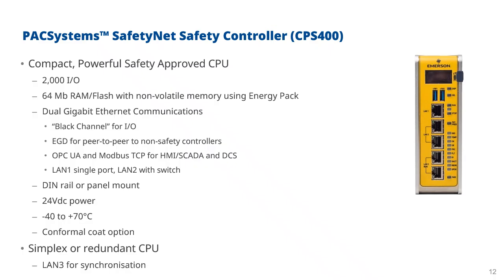So this is based on our existing Edge controller range. We've got the CPE 400 and the CPL 410. So it's actually identical hardware, but with slightly different firmware and different capabilities. And a key point there for safety, you'll notice we've got a yellow label. Now, this is a compact and powerful safety approved CPU. The initial release will handle up to 2000 I/O. In terms of memory, it's got 64 megabytes of RAM backed up with flash, and that's non-volatile memory using the energy pack. The energy pack is optional, so you don't have to use that.